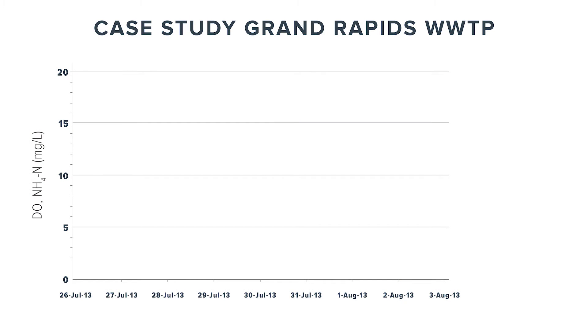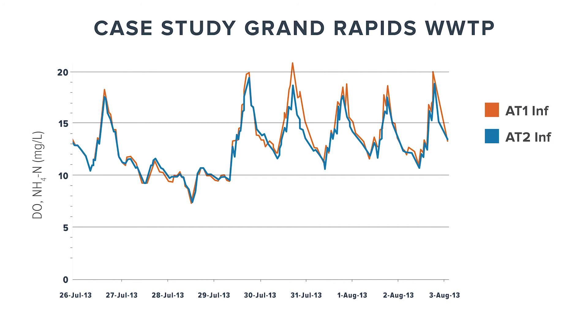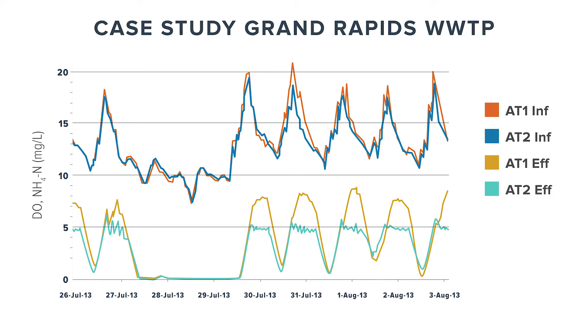As you can see in the graph, while the influent ammonium rates were actually fairly identical between the two aeration tanks, the effluent for aeration tank two — which had the probes — actually had a better effluent ammonium rate while reducing blower output. All of that ends up as a cost savings.